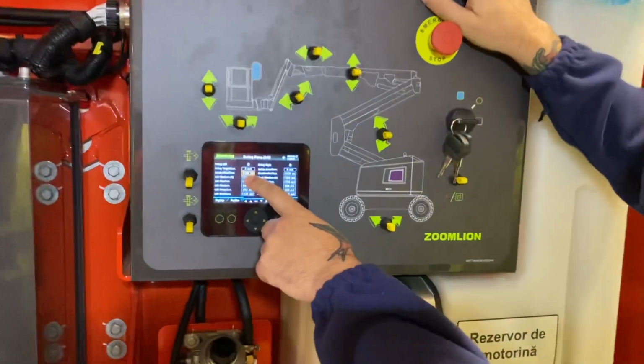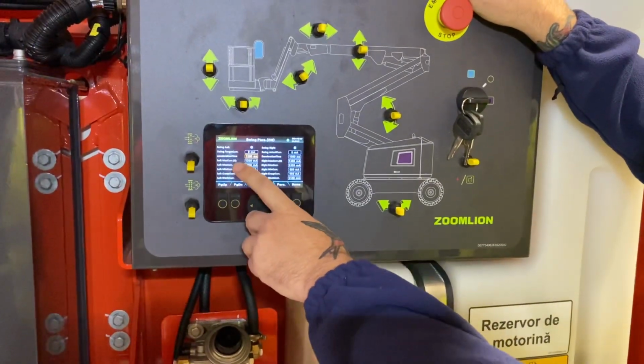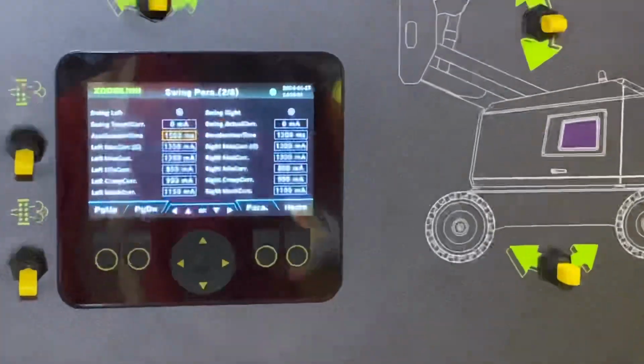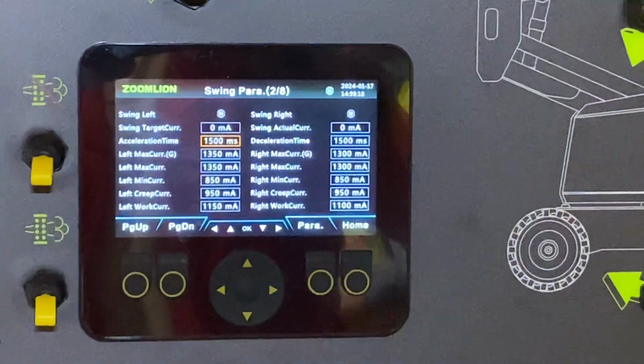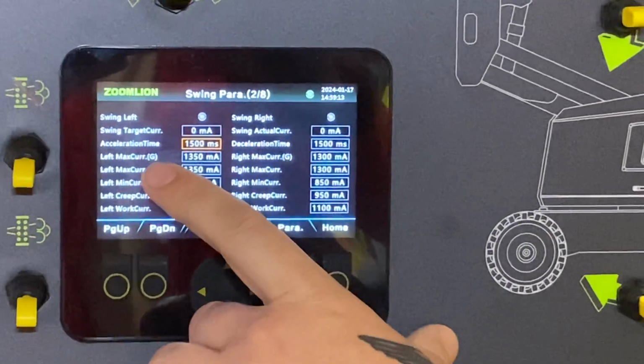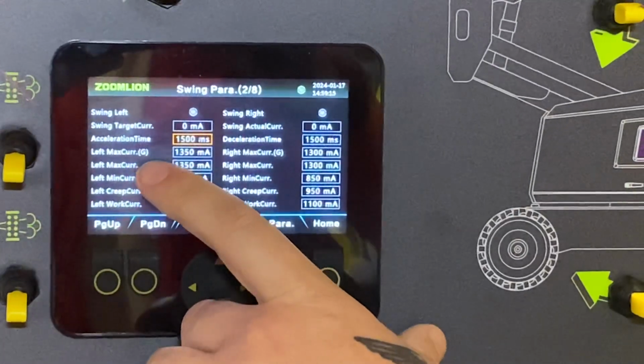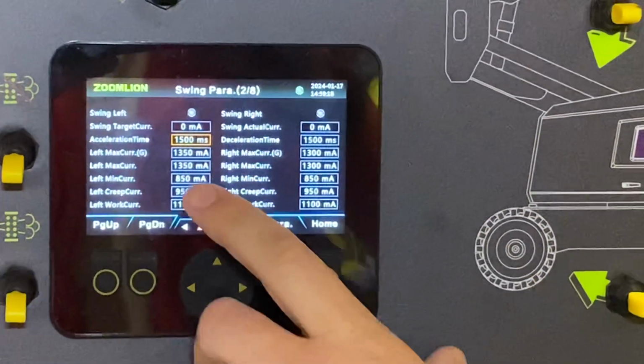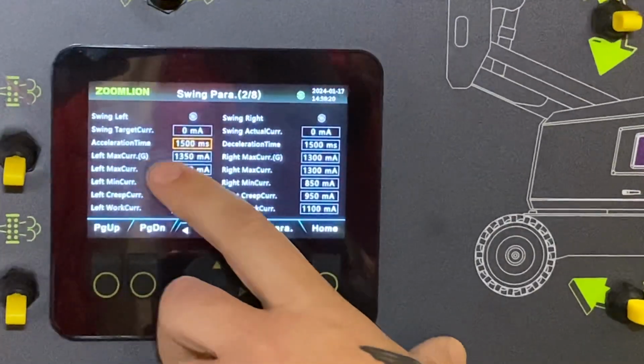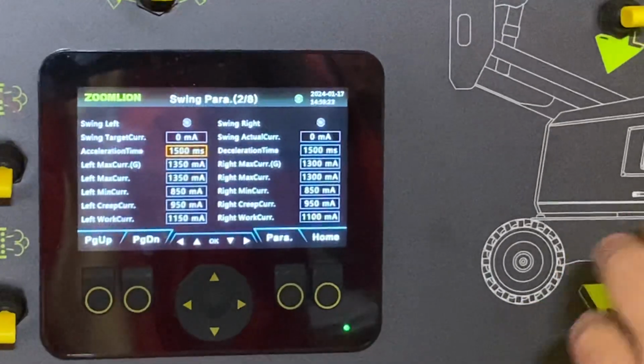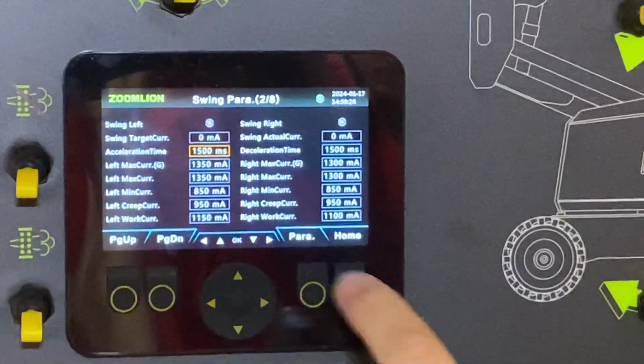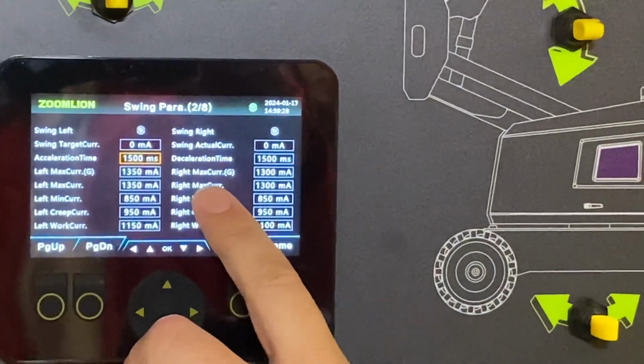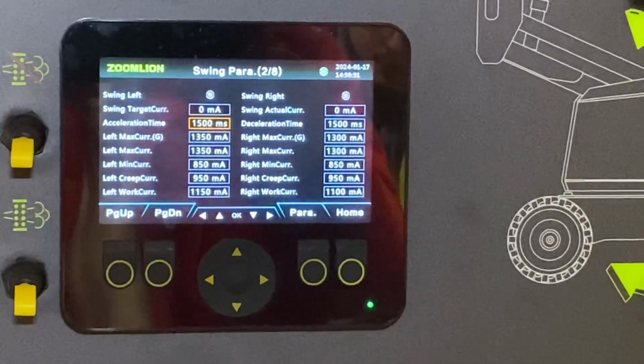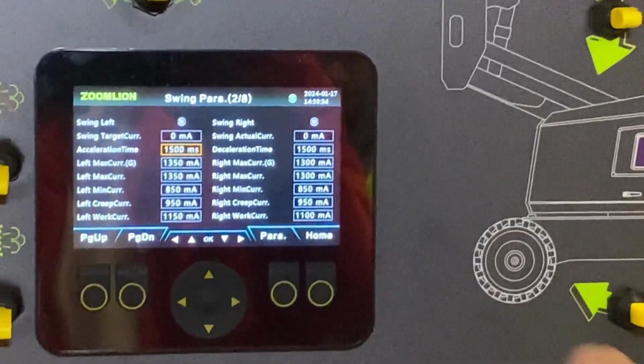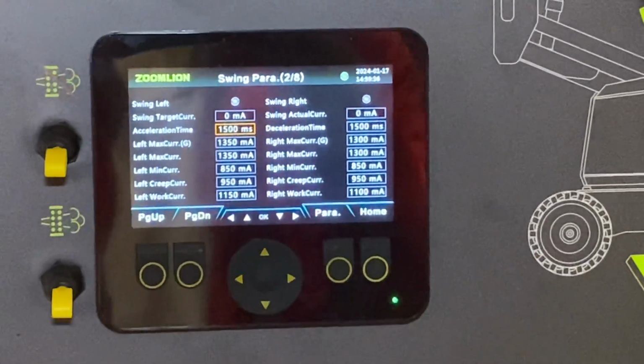Again, you can see the acceleration and deceleration times. Now, what's different on every page other than drive, because you can operate all functions except drive from the ground controls, so we need to be able to independently adjust the speed of the maximum current from the ground controls for every function. So for swing parameters, wherever you see a G next to max current left and max current right, that means from the ground controls, from the swing here. Where you see left max current and right max current without the G, that means it's from the platform. Okay, so if it says the G, it's from here. If there's no G, it's talking about the platform.